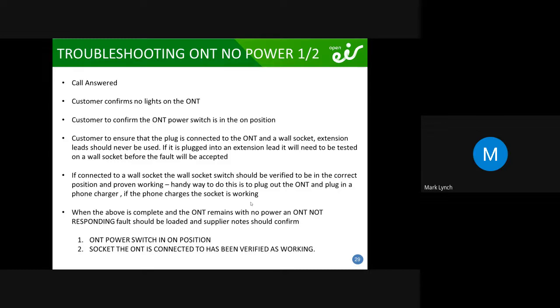Another thing that you won't come across often, but we've actually seen an awful lot of it in rural Ireland, is that people are using powered switches. So you're like extension leads that you plug into the wall and they have a circle around the plug, and you can set what time they work to what time they stop working at. You know, the wife or the husband might put them in, and then the partner then calls into you guys, unaware that they actually have them online. So that was another big driver of fail faults that we found, was the timed extension leads and the timed plug sockets.